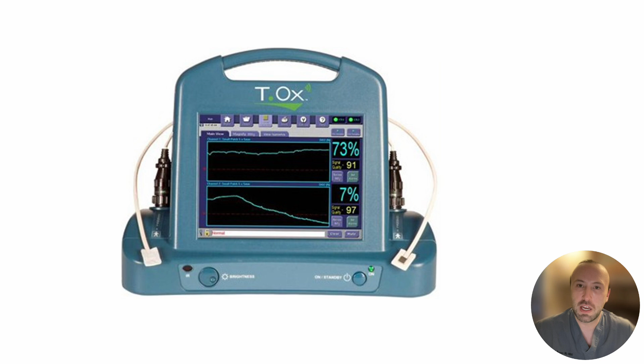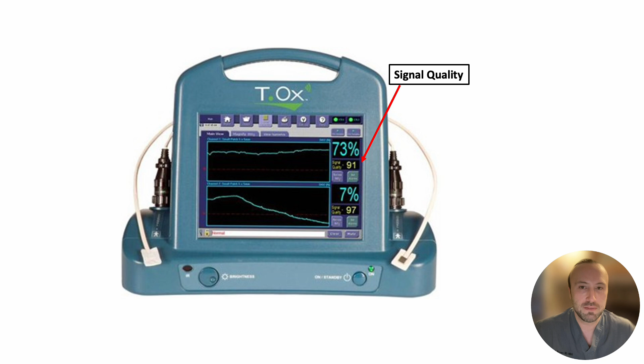The ViOptix monitor provides information on the flap oxygenation and perfusion. The signal quality value tells us whether or not the sensor probe is getting a good signal from the flap, telling us the reliability of the signal. Our goal for signal quality is 80 or better. Things that can cause a poor signal quality are poor contact of the probe with the skin, fluid between the probe and the skin, and bright lights directly on the flap.